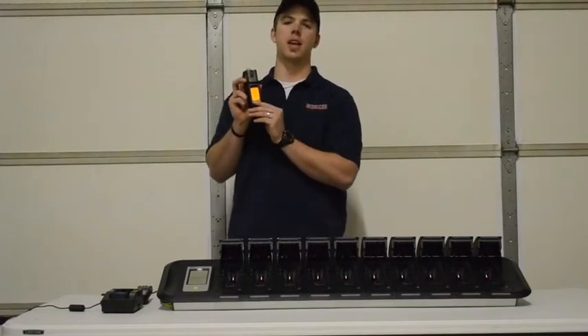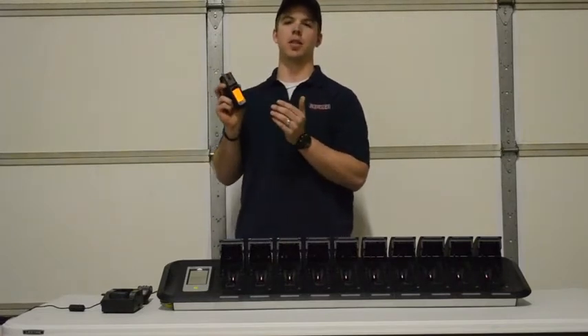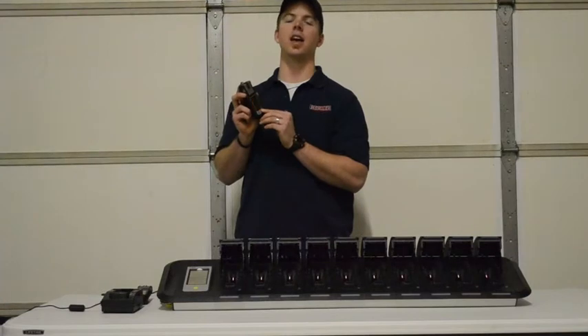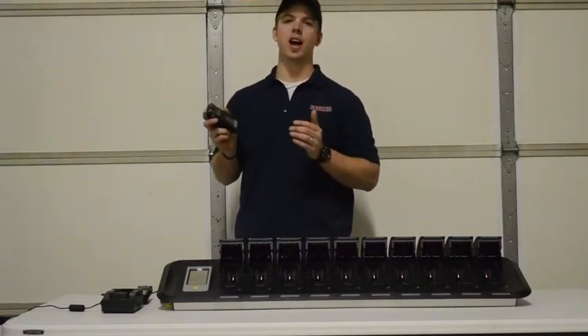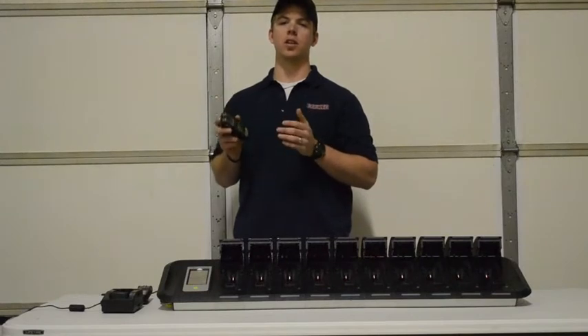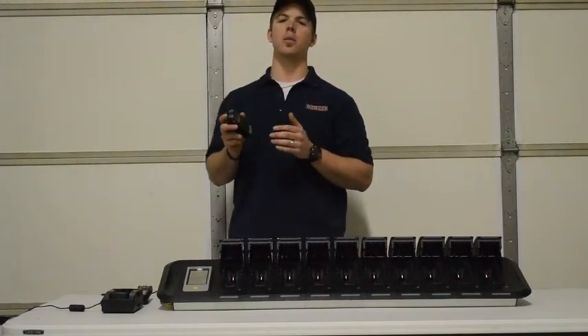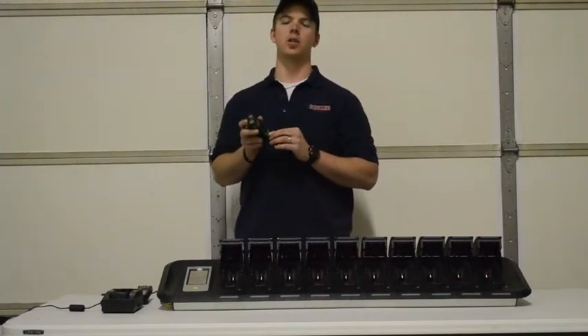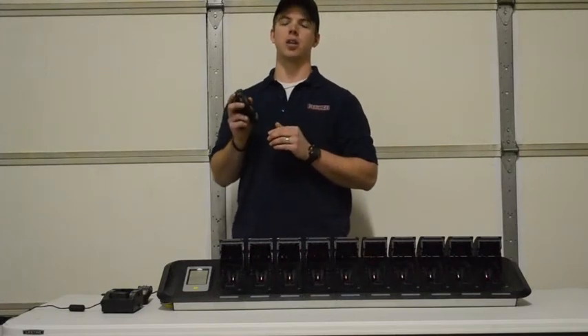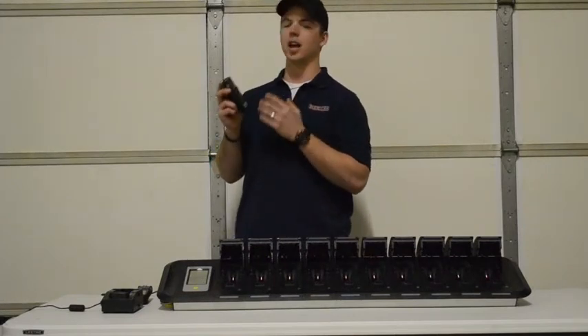The next alarm is the A2 alarm. For example, the CO sensor is set at 50 parts per million for the A2. A2s cannot be acknowledged, so what you need to do if you get an A2 alarm is exit the area immediately and go to a fresh air environment, and your monitor will reset itself and go back down to 0 or 20.9.